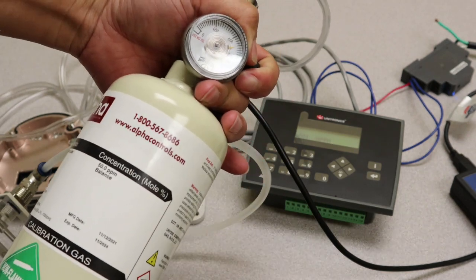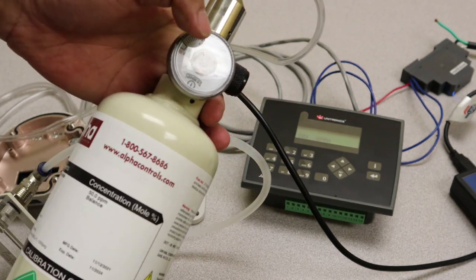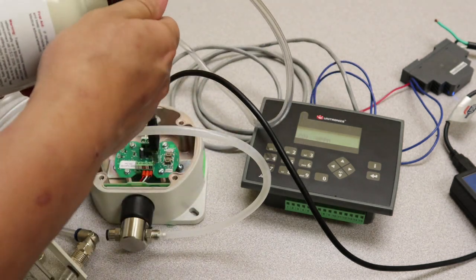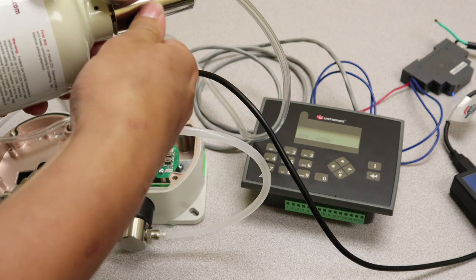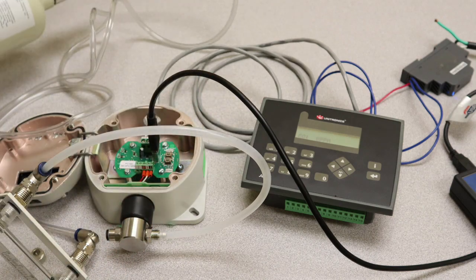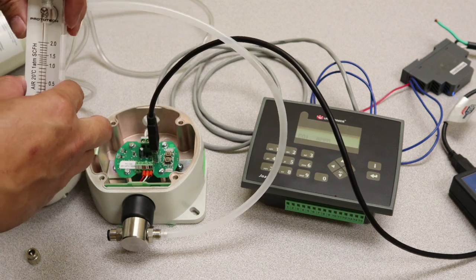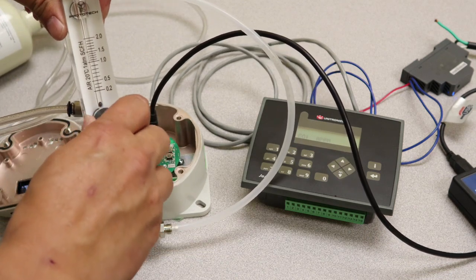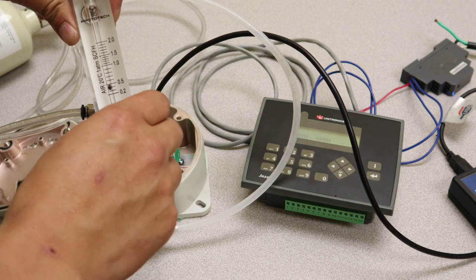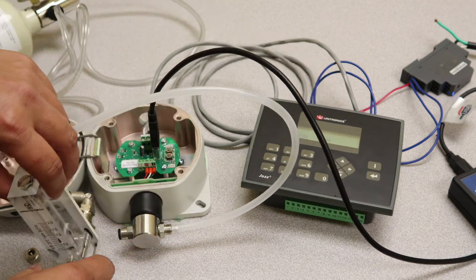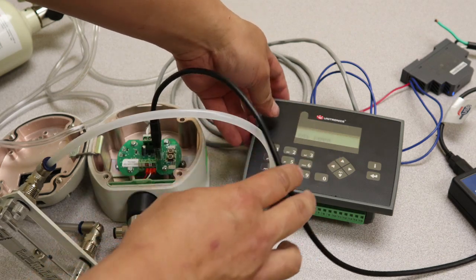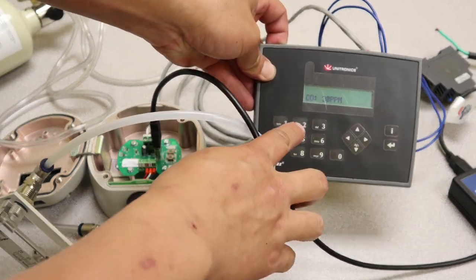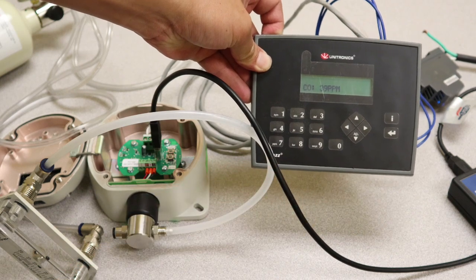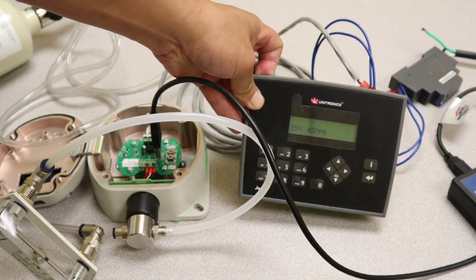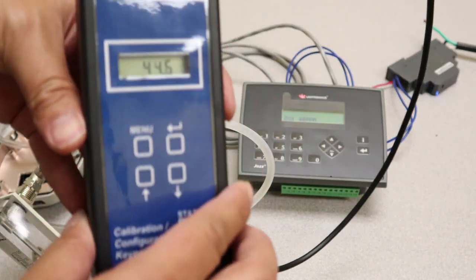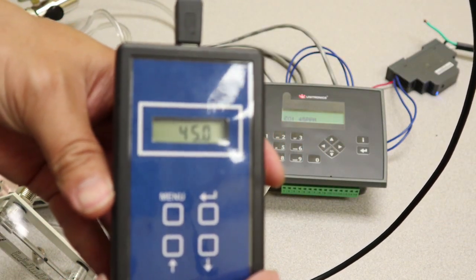Again, as you can see, the dial came right back up, meaning that there is gas inside the bottle. We're going to open up the bottle, and same thing, we're going to turn the flow meter up. Now, if you look at the PLC, the reading is already starting to climb. It's already at 40. And at the same time, the calibrator is also reading a much higher value now.